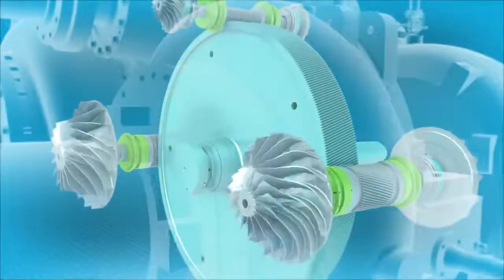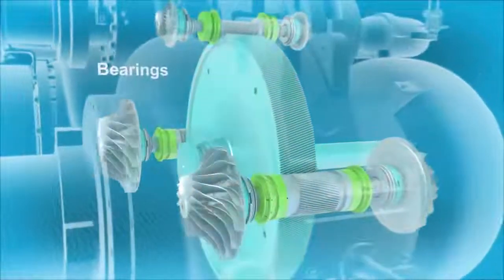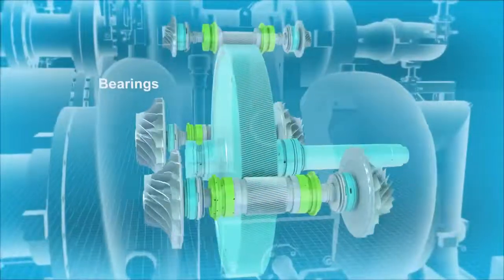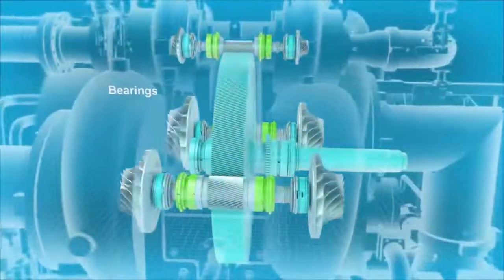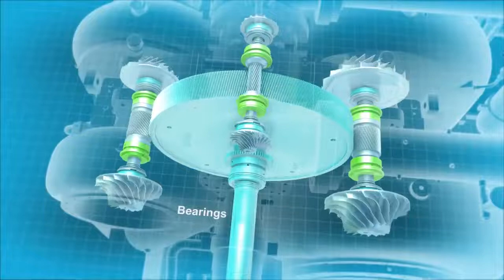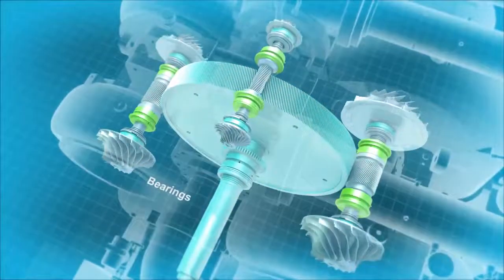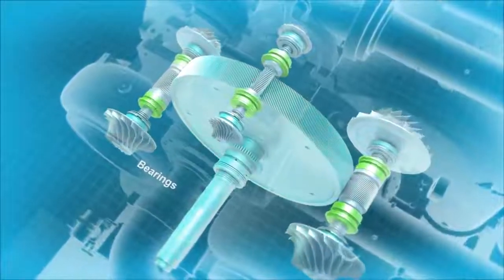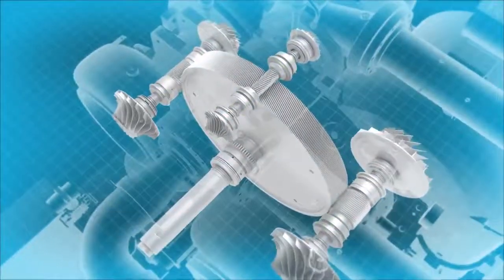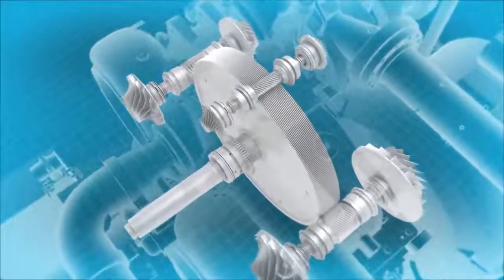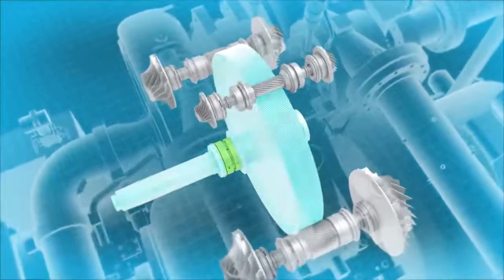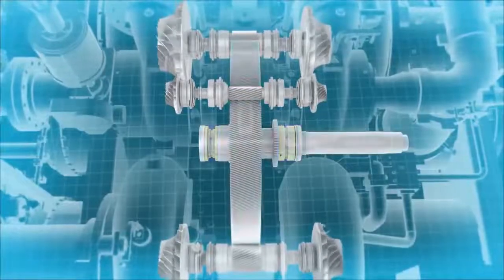High-speed rotors are supported by radial tilting pad bearings that eliminate virtually all vibration, while providing superior rotor stability and smooth rotation. Depending on the application, this can be a combination of radial and thrust bearings. The bull gear shaft rotates on multi-lobe sleeve bearings.